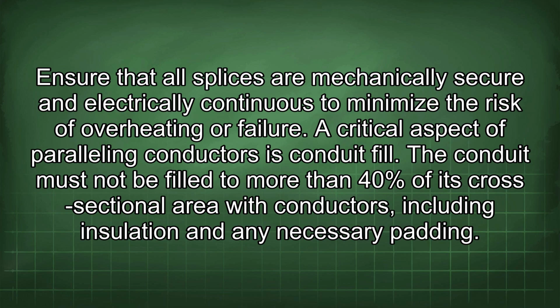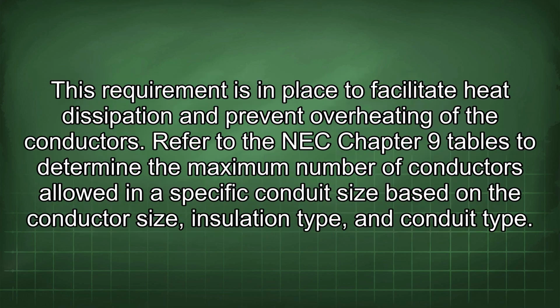A critical aspect of paralleling conductors is conduit fill. The conduit must not be filled to more than 40% of its cross-sectional area with conductors, including insulation and any necessary padding. This requirement is in place to facilitate heat dissipation and prevent overheating of the conductors. Refer to the NEC Chapter 9 tables to determine the maximum number of conductors allowed in a specific conduit size based on the conductor size, insulation type, and conduit type.